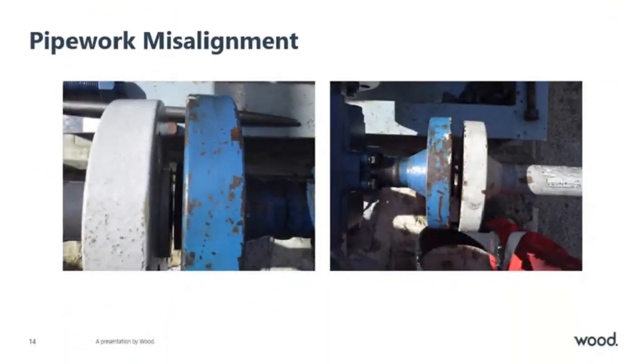When the pump heads were being changed, the technicians noticed that the pipework was misaligned and they needed to break flanges further away from the pump to alleviate those nozzle loads. But quite often the pumps were put back with considerable nozzle load remaining because there wasn't any other choice. The system needed to be repaired and the standby pump would start to fail also.